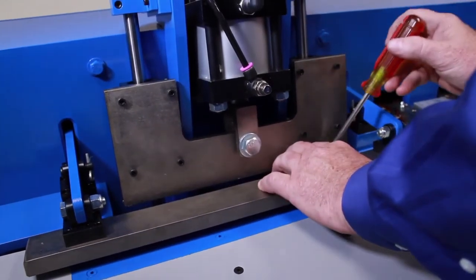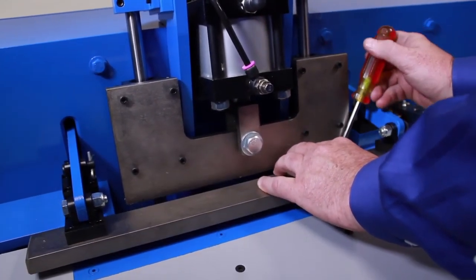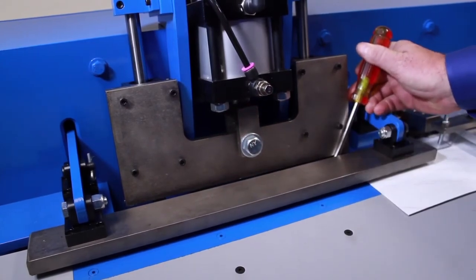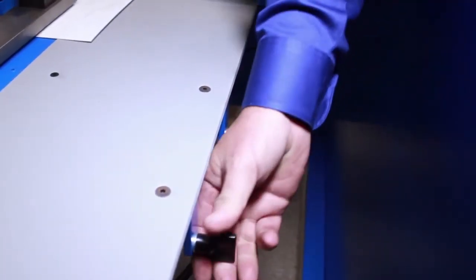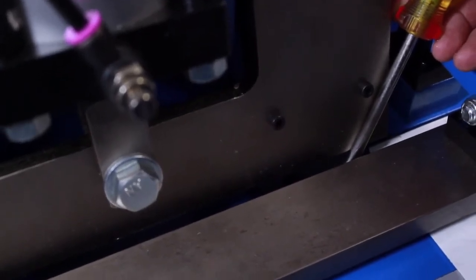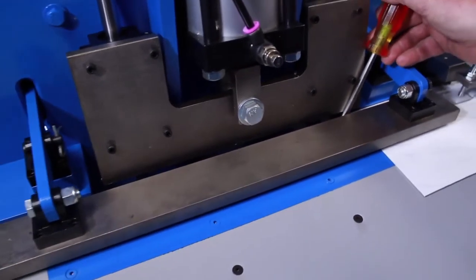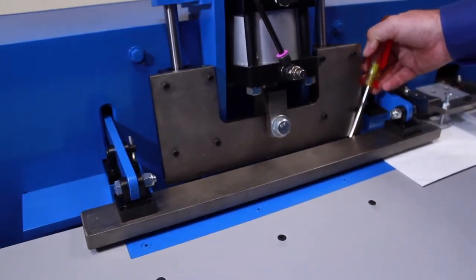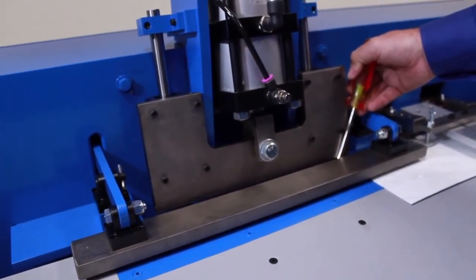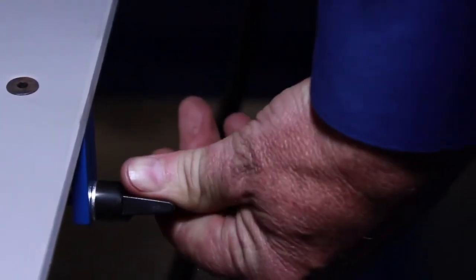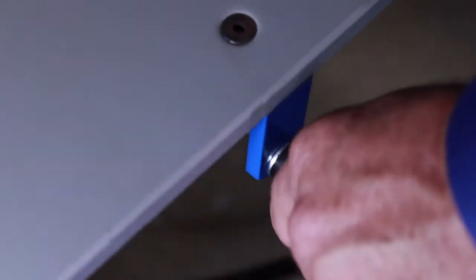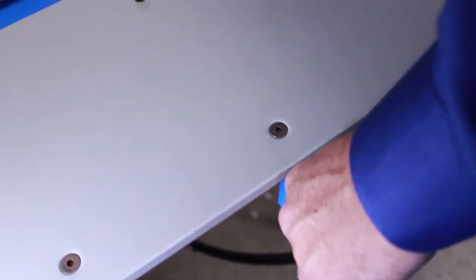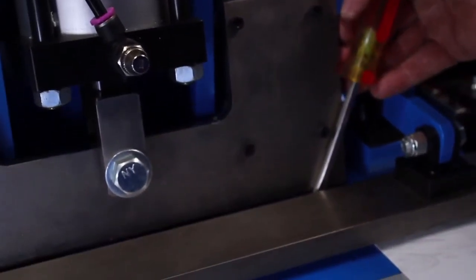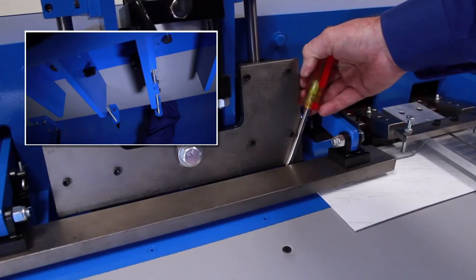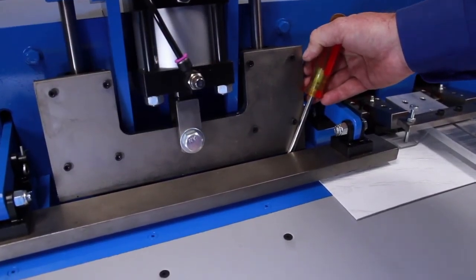Then, once they're loose, stick a screwdriver in between the die and the flanging ram on one side. Make an adjustment to the thumb bolt. And I'm using the screwdriver as pressure, as to keep any backlash out of the threads. And if you turn this thumb bolt clockwise, it'll pull the flanging ram closer. Counterclockwise, it pushes it away. Now I can feel the blade moving in my right hand. Keep pressure against the blade and tighten my thumb bolts located underneath the machine. And that's how you adjust the flanging ram.